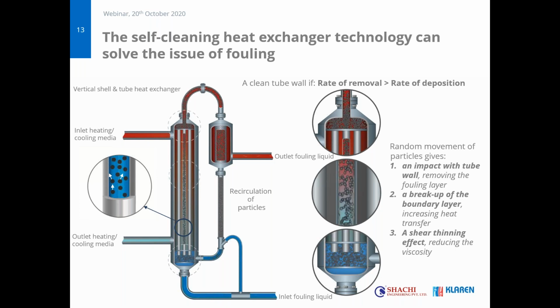But it's a light scouring action, so it will not erode the tube walls. It's a light scouring action that keeps the tube wall clean and effectively makes sure that a layer cannot develop, because the cleaning mechanism is not so aggressive that it could really clean a tube that already has a thick layer. No, we need it from the beginning. We also need it from the beginning because our system is an integral part of the heat exchanger design.